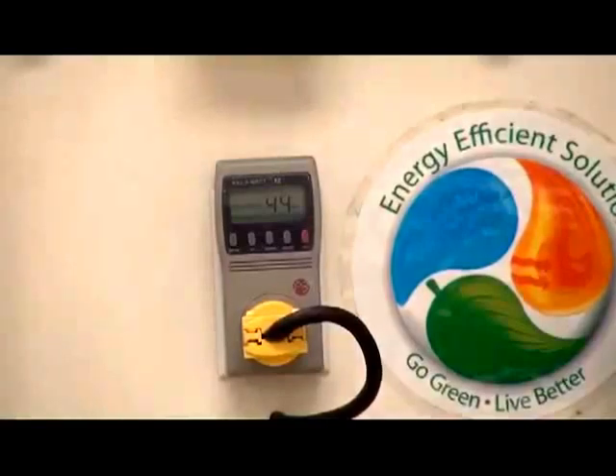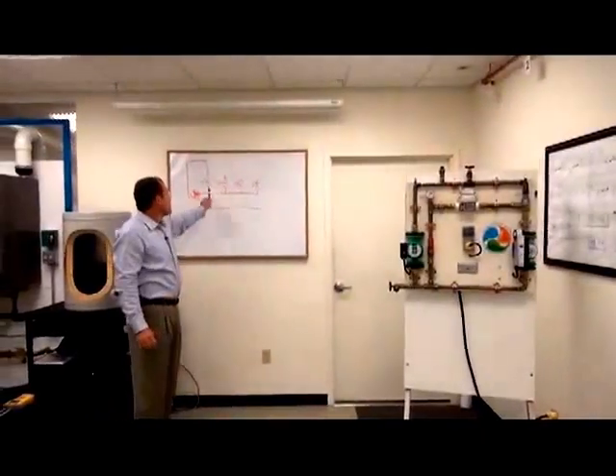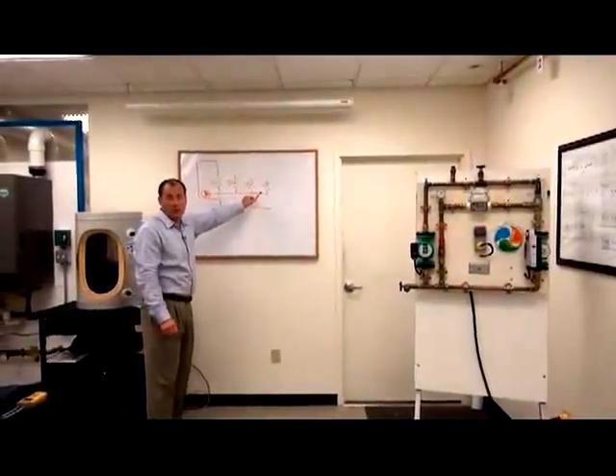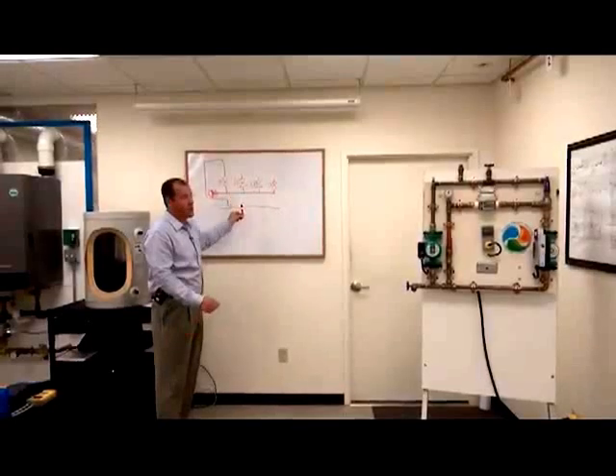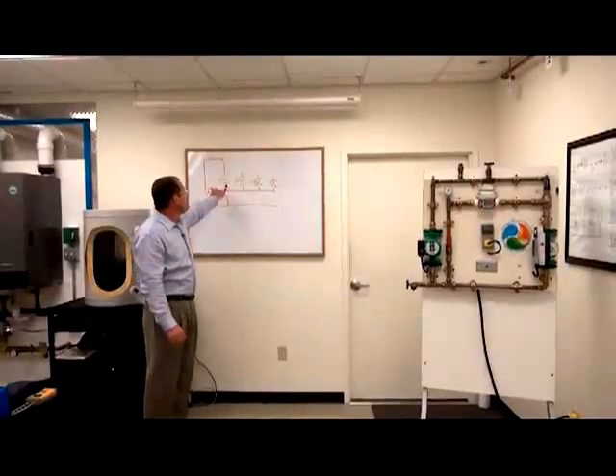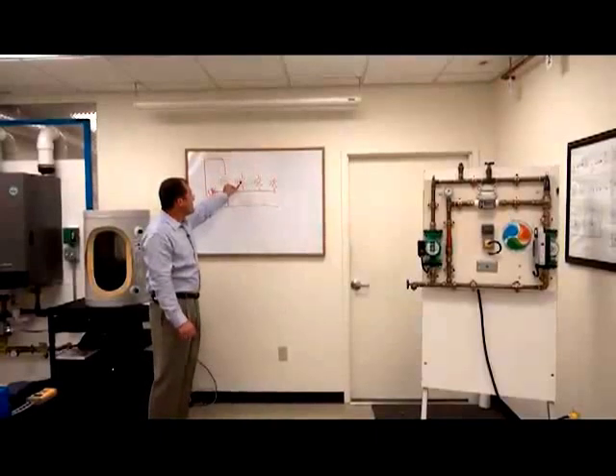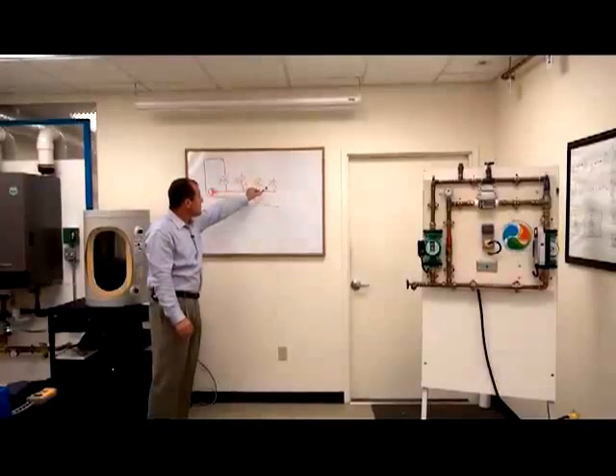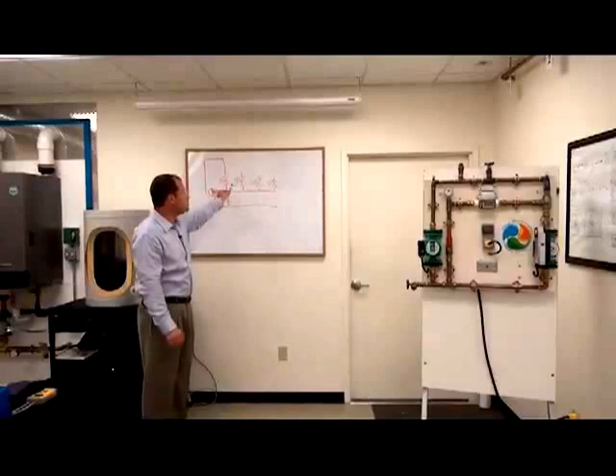And when you have this type of strategy where these valves are opening and closing, most of the year, only at the coldest day of the year would you typically have all of your zones open. Most of the time you might only have one or two zones open at a time. So it's nice for this pump to know that it only needs to provide enough flow for these two zones or these two zones or this one zone. So it speeds up and slows down as these valves open.